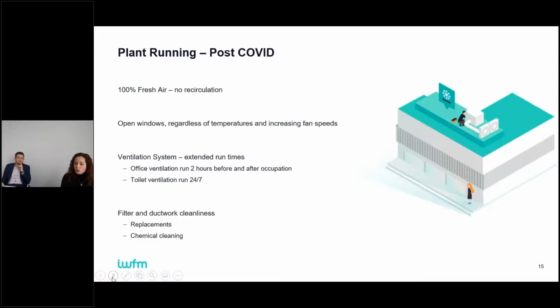A frequent question we receive is about the strength of filters to trap particles and airborne pathogens. Our view is that if you replace your filter with a denser material than your HVAC system was built for, it creates high resistance in your air handling unit, makes the plant run under more pressure, reduces life expectancy, and increases risk of plant failures. So what we advise is replacing like for like.